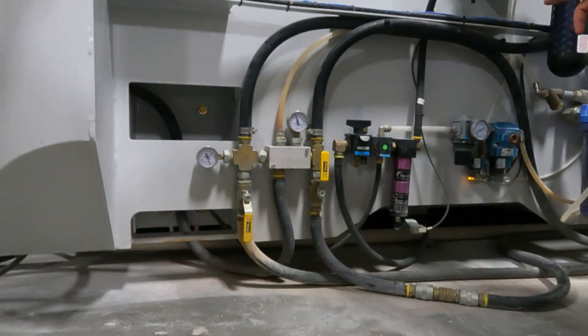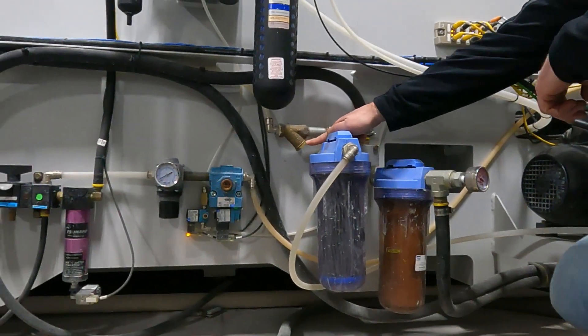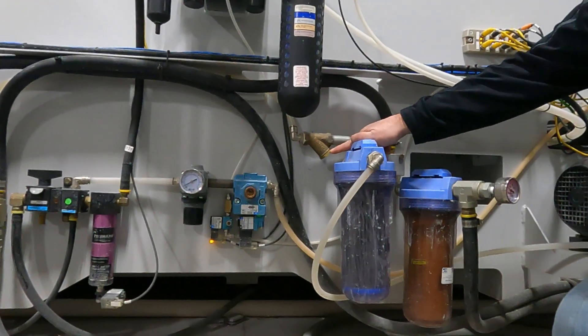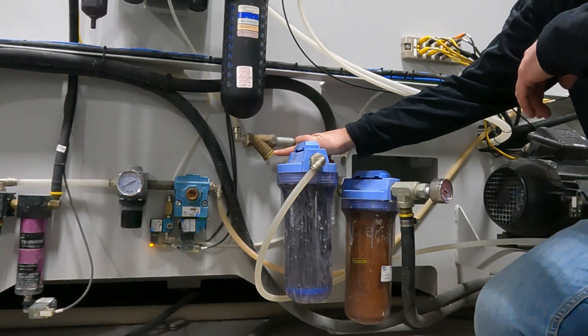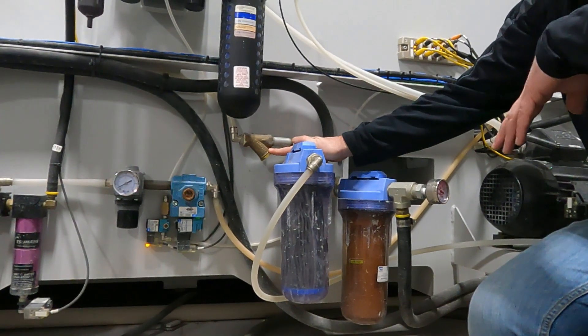From there then, this line comes over to your Y strainer here. And in this Y strainer, you can remove this nut. And that is a screen that you need to clean and or replace if it gets real bad there.